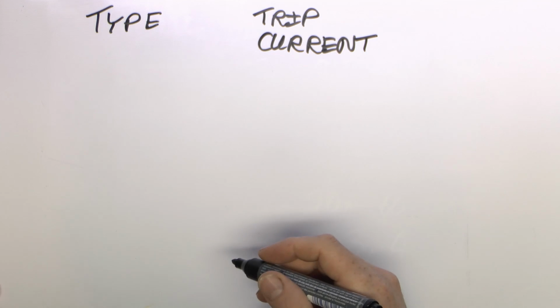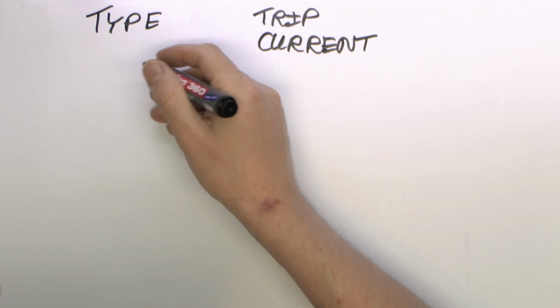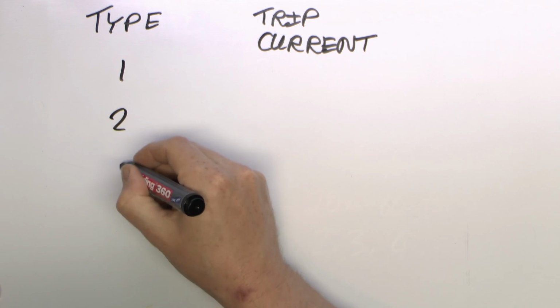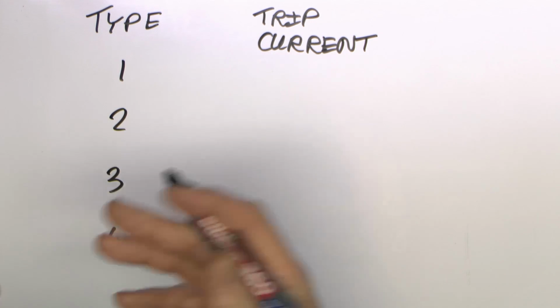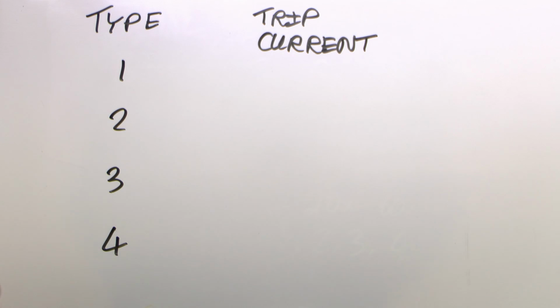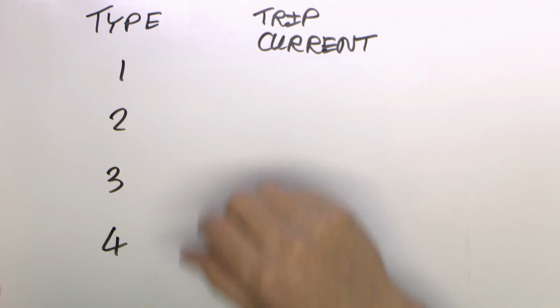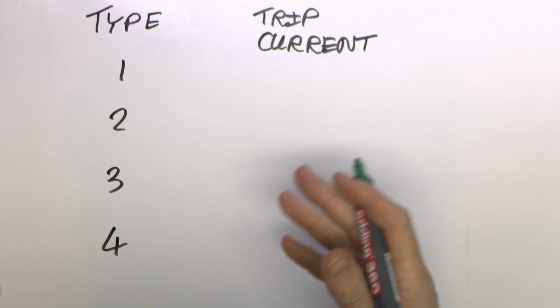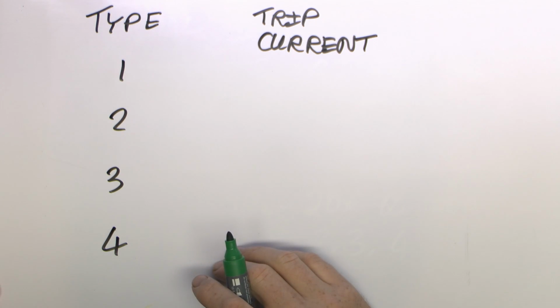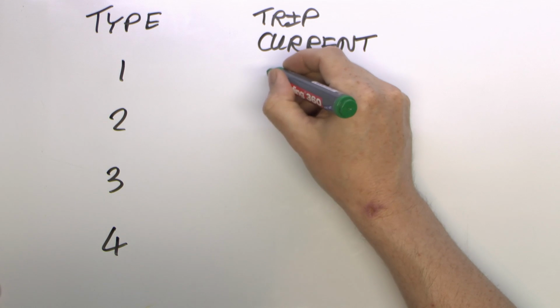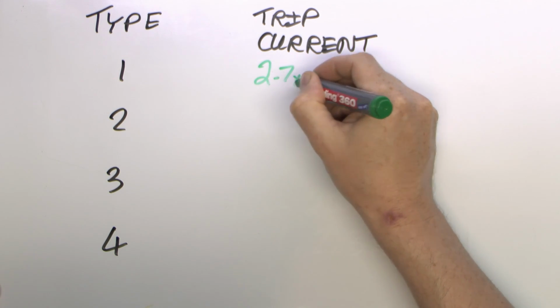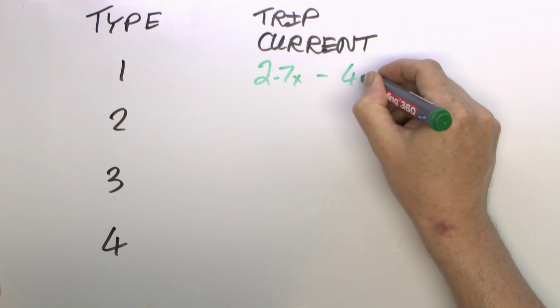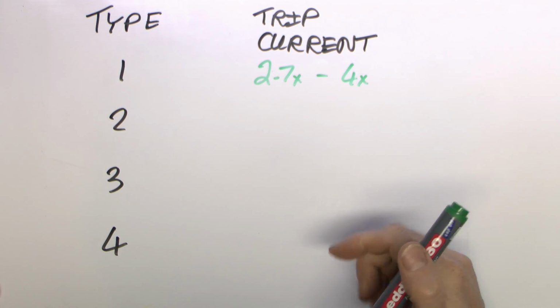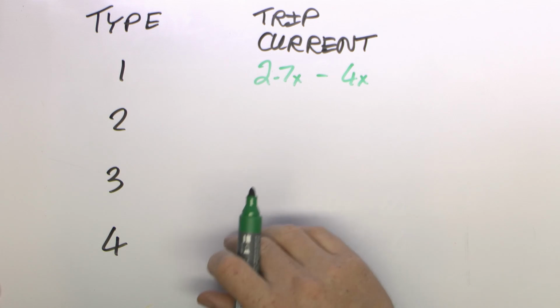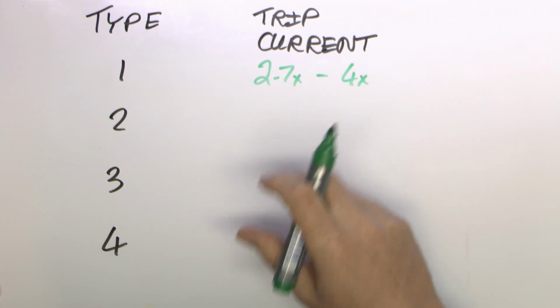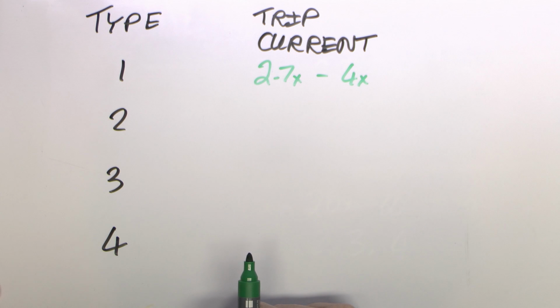Now the older type of classification for circuit breakers was a numeric system, and that was basically types 1, 2, 3 and 4, and so they don't make those anymore, but there's still plenty of them out there. It's quite common to see those, certainly in older installations, and it's a very similar arrangement, although the actual ratings are slightly different. And the Type 1 is going to trip somewhere between 2.7 times and 4 times the current. So that's roughly equivalent to a type B, although the actual numbers are slightly lower because that was obviously 3 to 5 there. So quite common to see those in many domestic type properties.